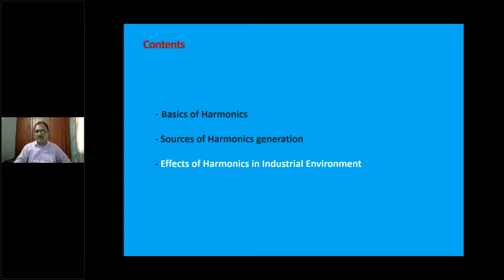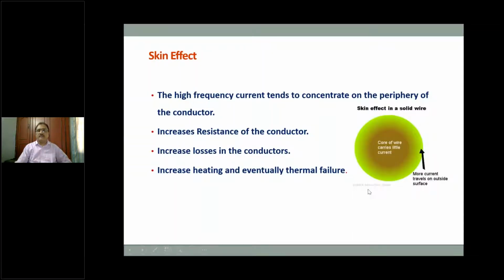So we'll see what the effect is. Why is it important that we address the generation of harmonics, and how do we see the effect of harmonics? If you touch a cable, you will find that the cable is very hot, because the harmonic current flows through the periphery of the cable. The core of the cable will not carry the current, so it will not be hot, but the periphery will be very hot. So for any nonlinear load carried by a cable, invariably you will find that the core is cold and the periphery of the cable is hot.